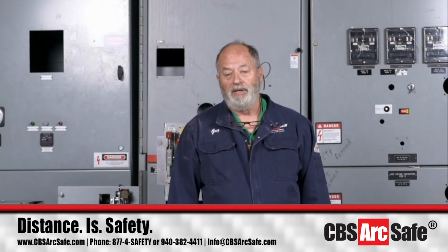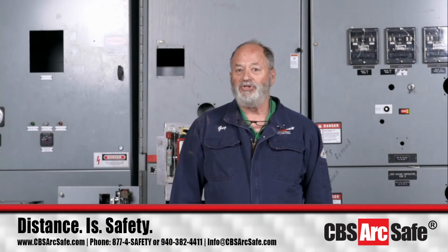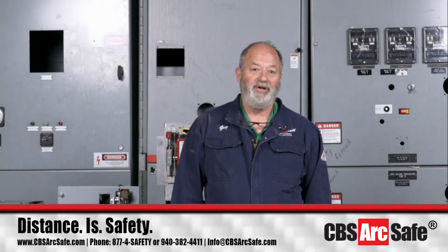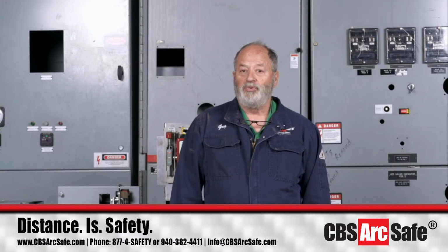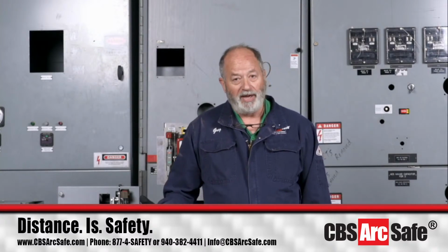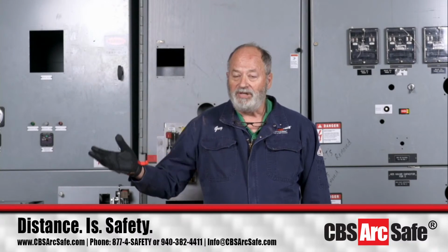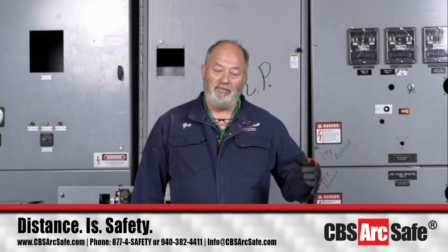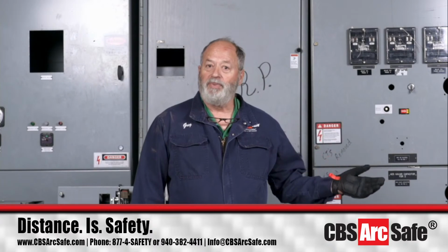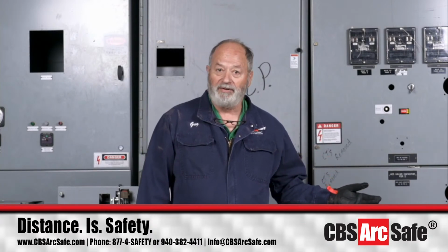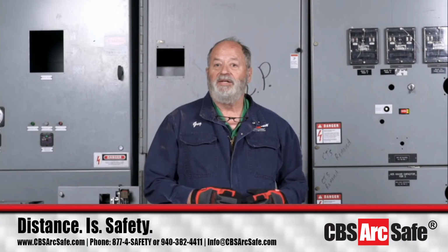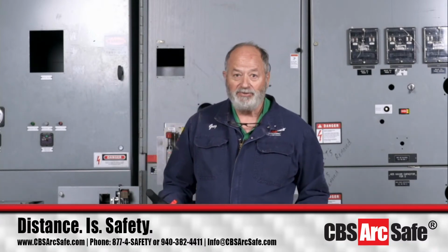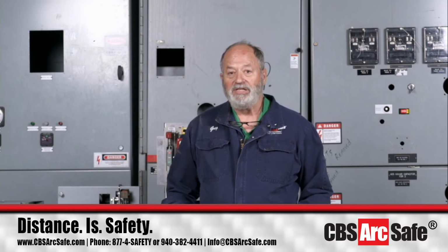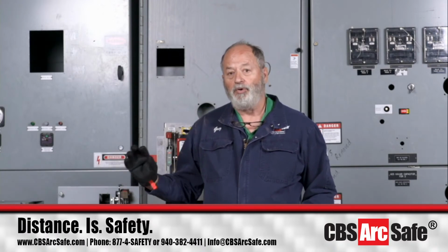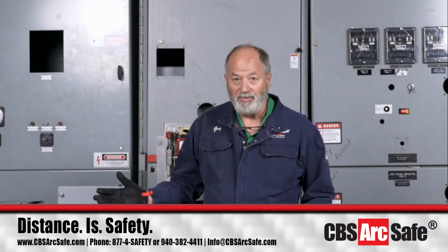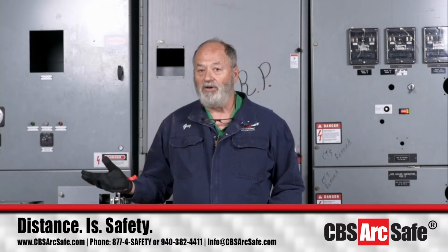SquareD actually started out as a motor control center manufacturer. We've done stuff for SquareD Model 3, Model 4, and we're going to show you one item. They moved up to Model 5 and Model 6. They got into the bolted pressure switch by working with a company called Barkley out of Ohio and bought that up. When they got into air circuit breakers, they first had a license from Westinghouse, and you'd sometimes see a DS with their name on it, or a K-line breaker with their name on it, because they licensed that from ITE also.